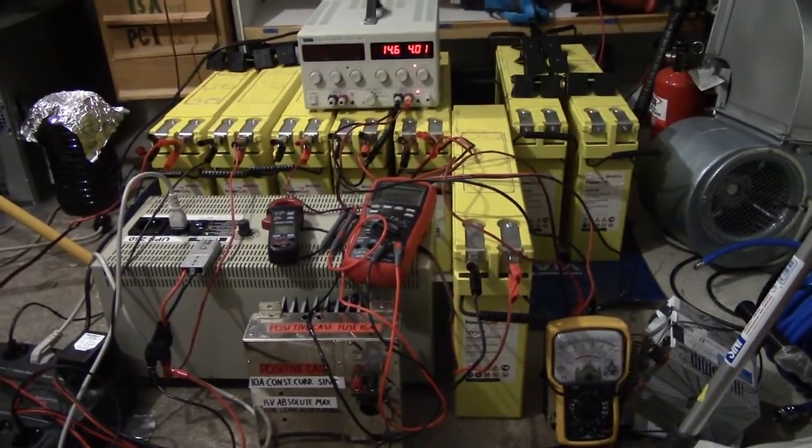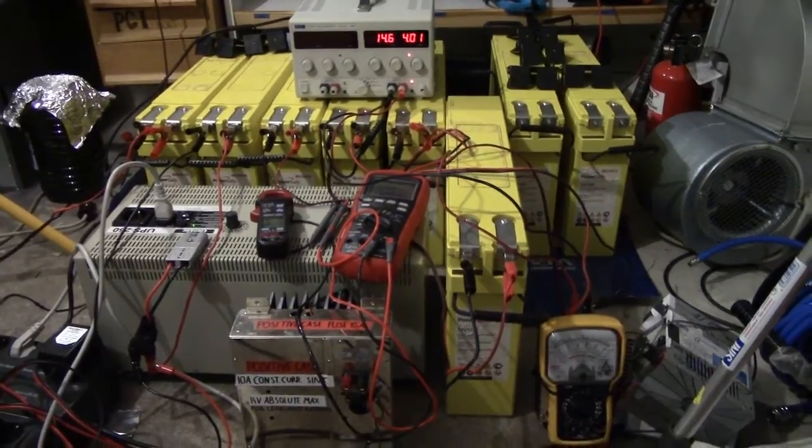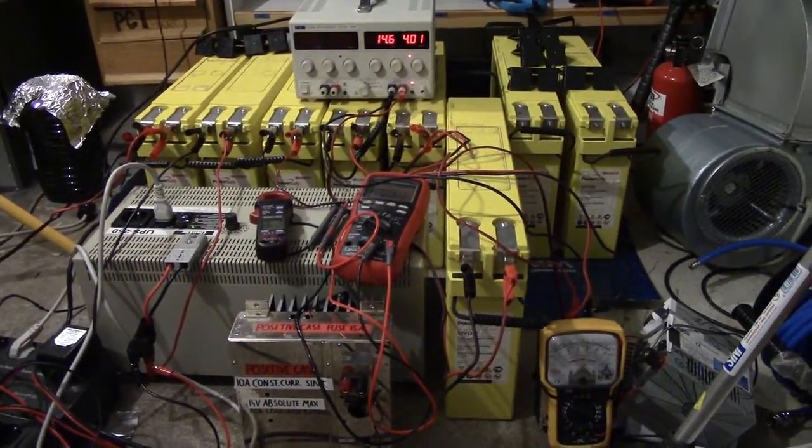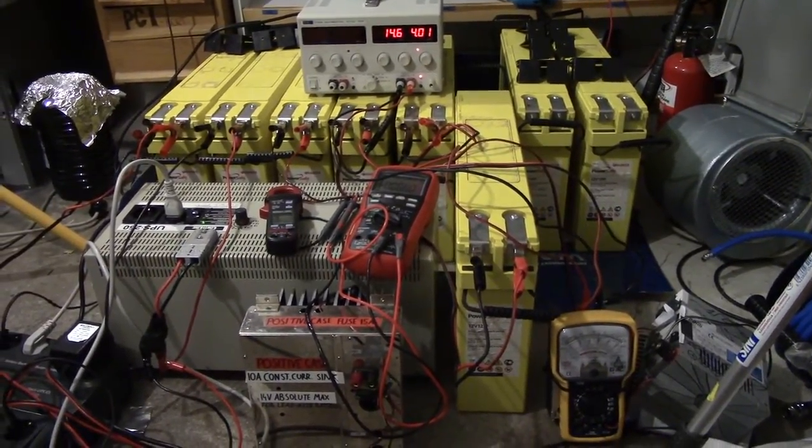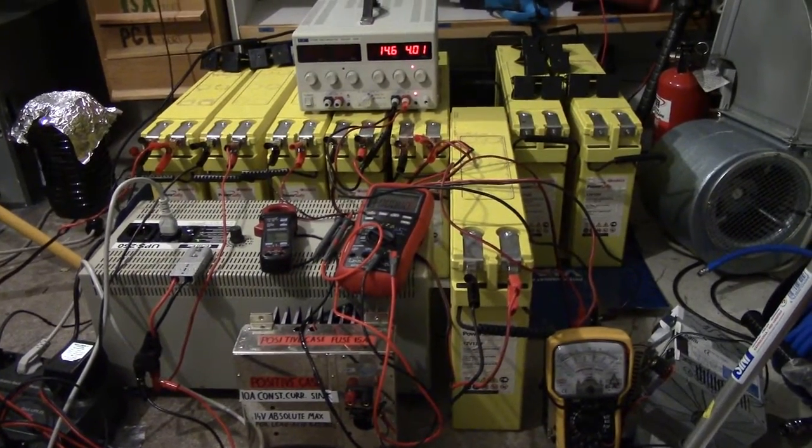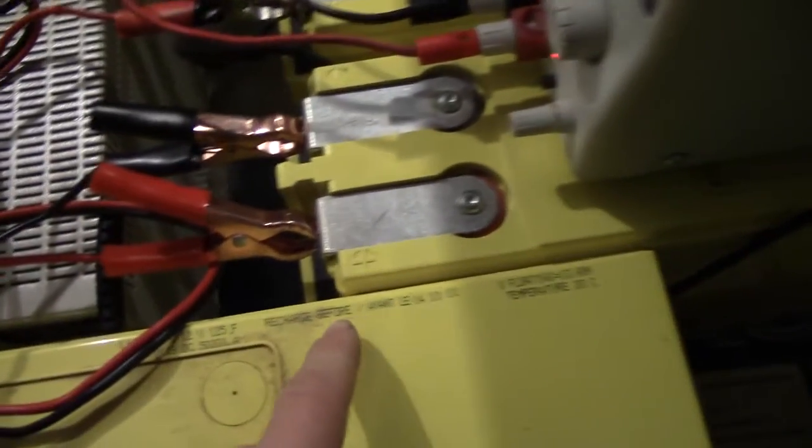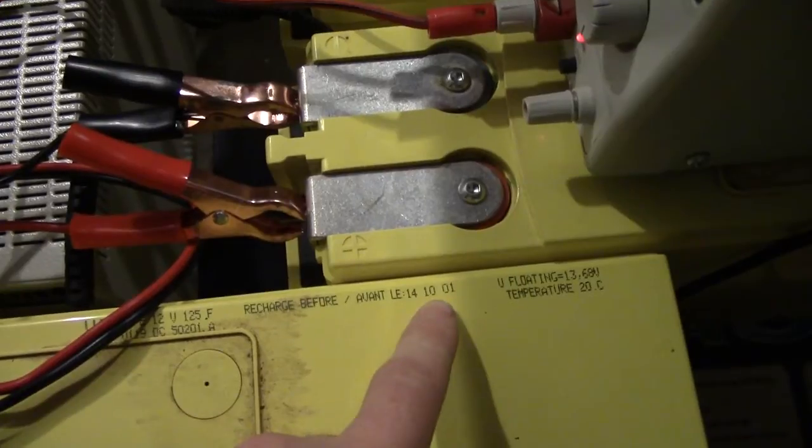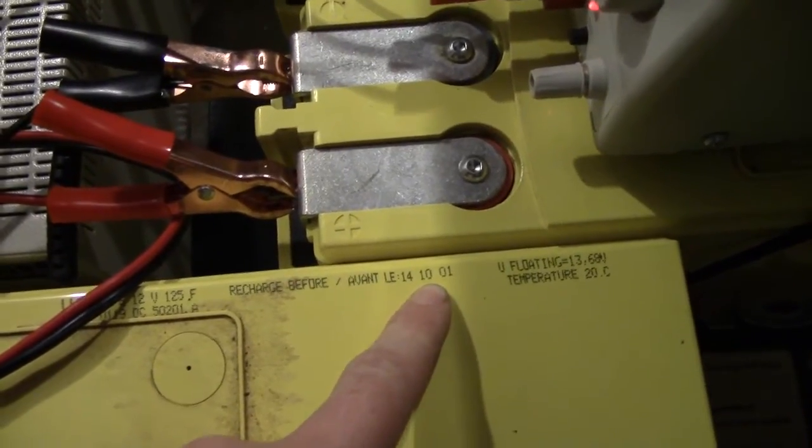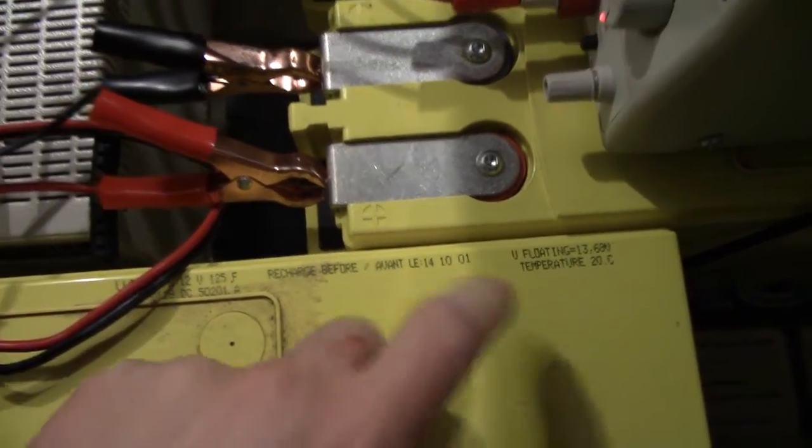They are not new, they are in fact beyond their 12 year specified service life judging from this little stamp on them which says recharge before 14th 10.01, so these are probably 14 years old.